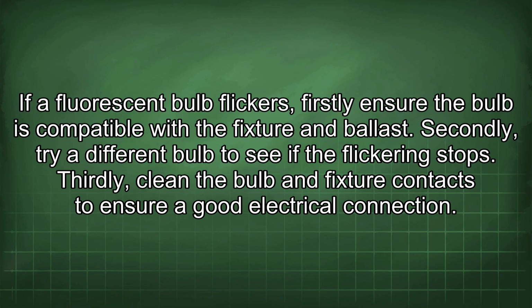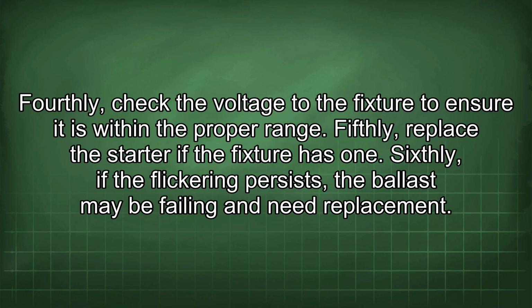If a fluorescent bulb flickers, firstly ensure the bulb is compatible with the fixture and ballast. Secondly, try a different bulb to see if the flickering stops. Thirdly, clean the bulb and fixture contacts to ensure a good electrical connection. Fourthly, check the voltage to the fixture to ensure it is within the proper range. Fifthly, replace the starter if the fixture has one. Sixthly, if the flickering persists, the ballast may be failing and need replacement.